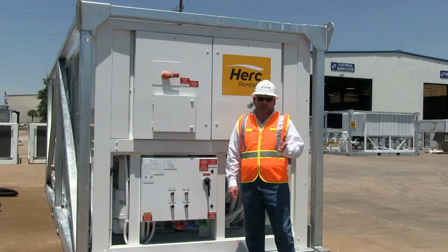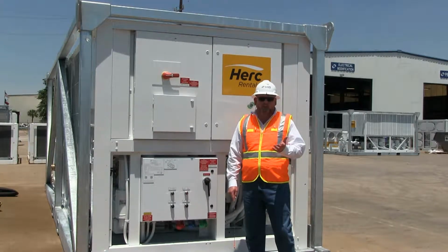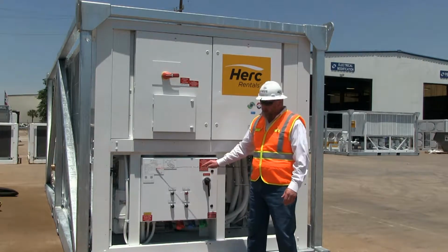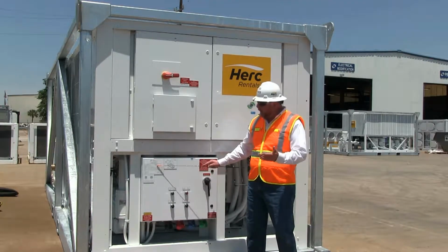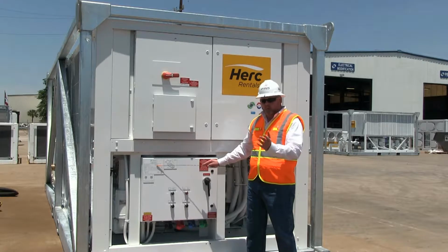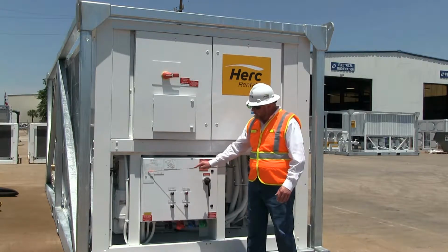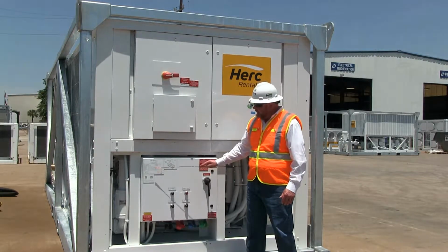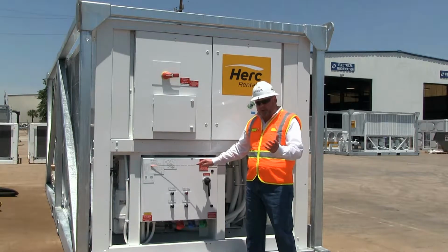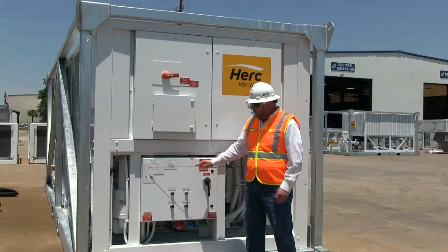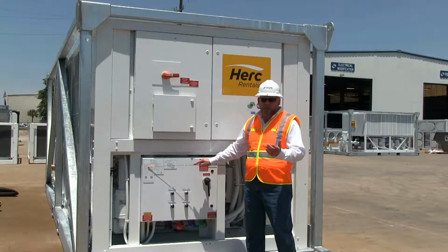The next step in our setup is going to be to verify the power requirements. The MCA, or minimum circuit ampacity, required to run the entire assembly with the integrated pump is clearly labeled here on the CAPS data tag. This particular machine takes 379 amps of power, and the MOCP, or maximum overcurrent protection, is 450 amps.